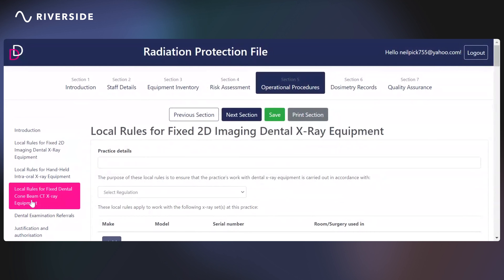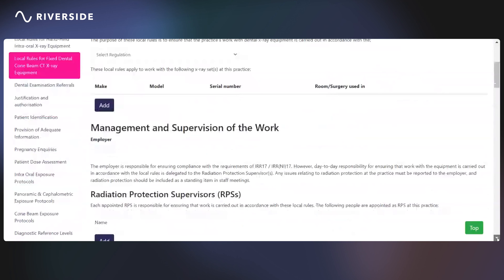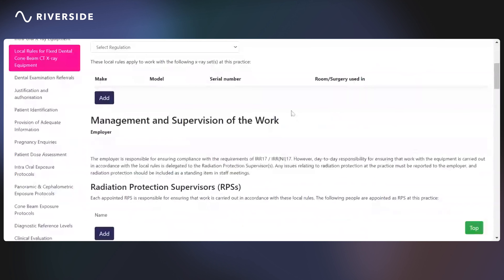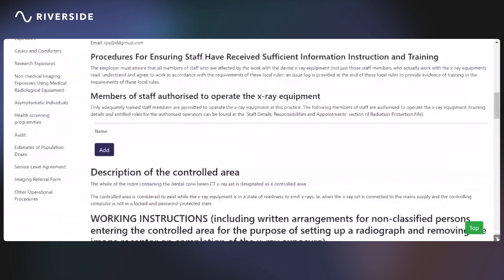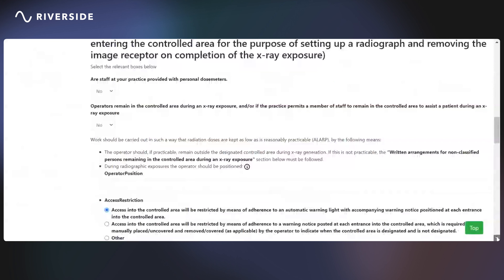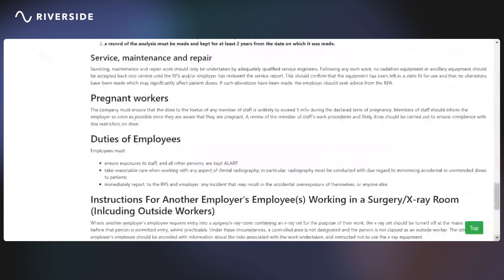There are local rules for fixed cone beam CT units. We talk you through the process and you enter the details that are required: who can use the equipment, who the radiation protection supervisors are, what the description of controlled areas are, what your working instructions are, dose investigation level, contingency plans, what to do if something goes wrong, servicing, maintenance, repair, pregnant workers, duties of employers and employees, and instructions for another employer's employee working in an x-ray room.